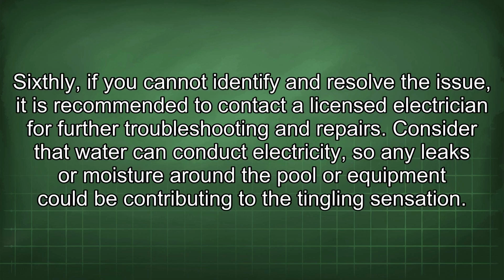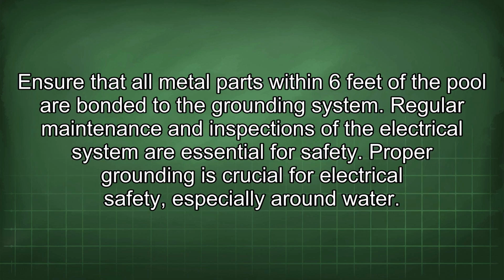Sixthly, if you cannot identify and resolve the issue, it is recommended to contact a licensed electrician for further troubleshooting and repairs. Consider that water can conduct electricity, so any leaks or moisture around the pool or equipment could be contributing to the tingling sensation. Ensure that all metal parts within 6 feet of the pool are bonded to the grounding system. Regular maintenance and inspections of the electrical system are essential for safety.